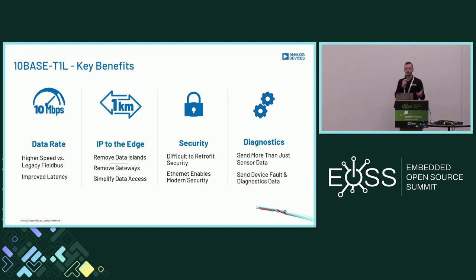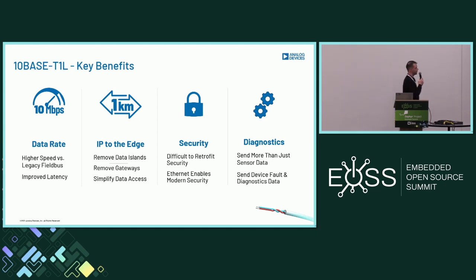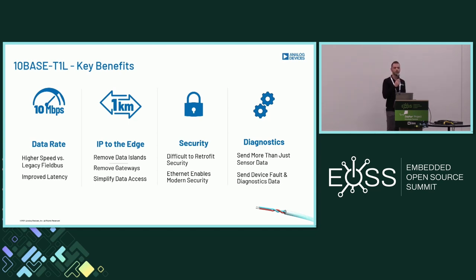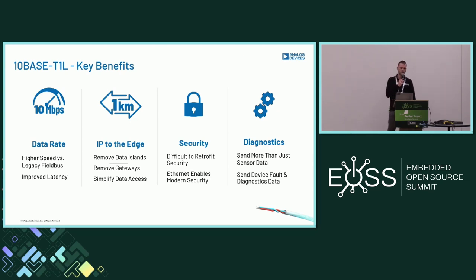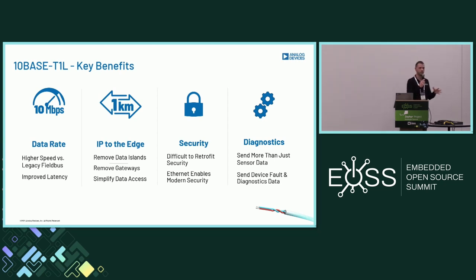Looking at 10BASE-T1L's key benefits in four areas: data rate, bringing IP to the edge, security, and diagnostics. On data rate — 10 megabits per second may not sound impressive given gigabit ethernet today, but the key comparison is to legacy fieldbus protocols like RS-485. Over distances of one kilometer, RS-485 operates in the kilobit per second range, so 10 megabits per second is a sizable improvement and is often plenty for sensor and edge device applications. The improved latency is also important for applications like control loops requiring millisecond latency.